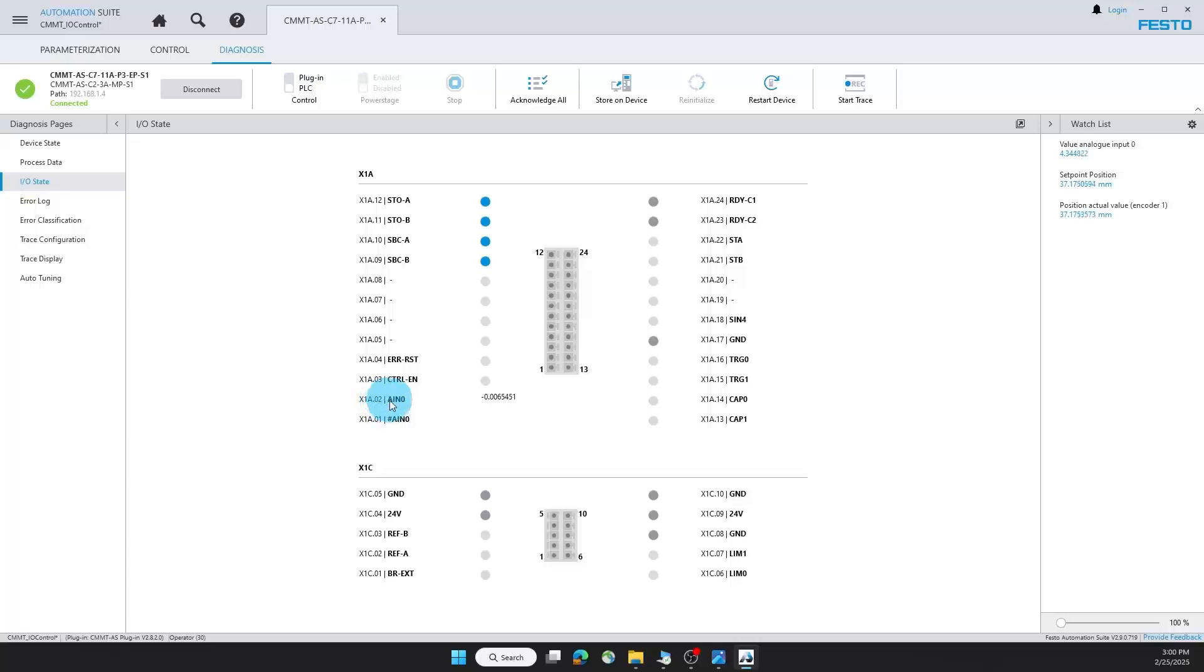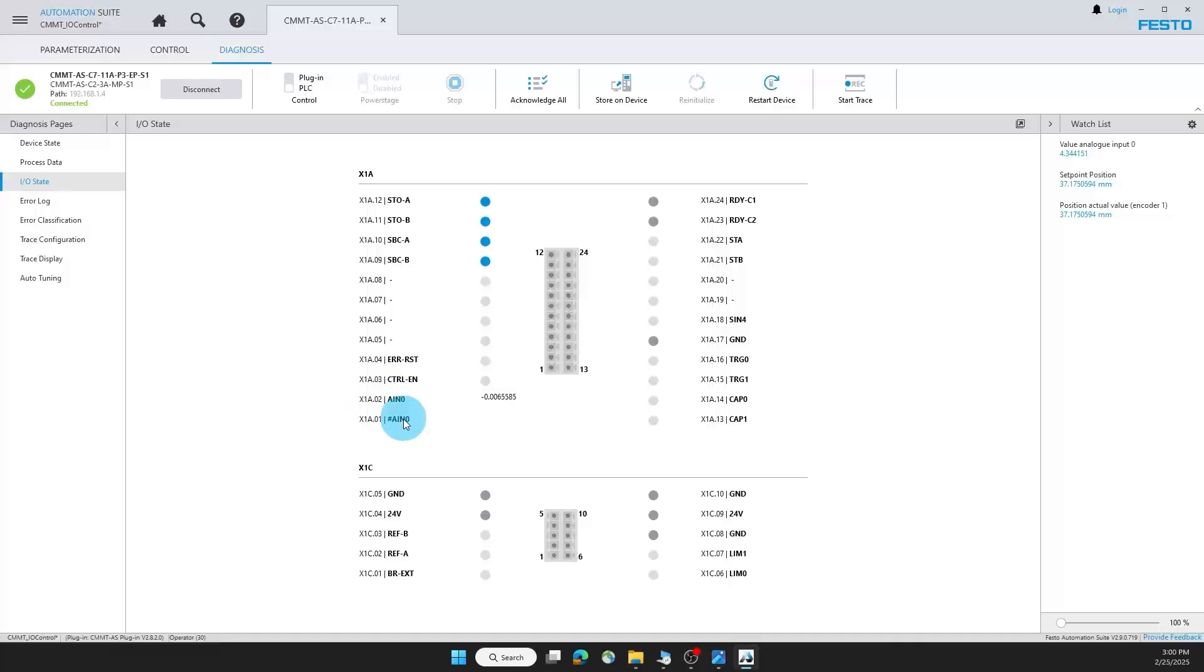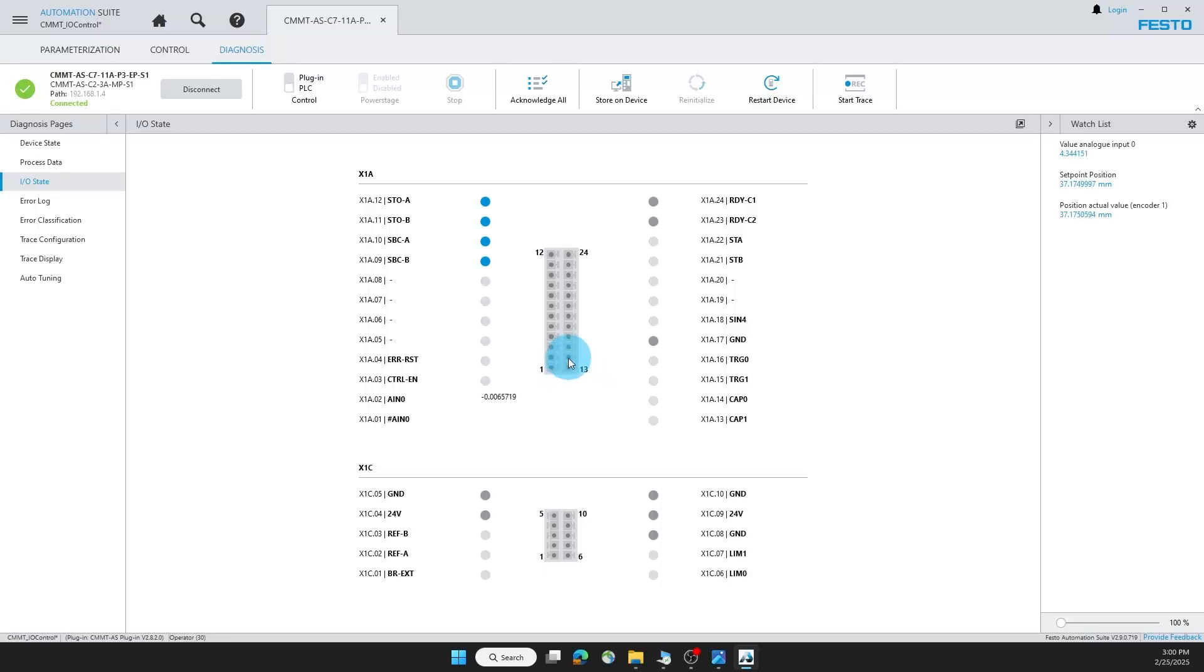Pins one and two are for my analog input, which are only necessary if you're running an analog control. This will be my minus 10 to positive 10 volt connection, and here's a common for my DC for reference. On this side here I have cap zero and cap one, which are my two momentary push buttons for my retract and extend signals. On one end I have 24 volts and now I'll feed 24 volts directly to each of these pins when I request. Now I can show you how this I.O. control is set up.